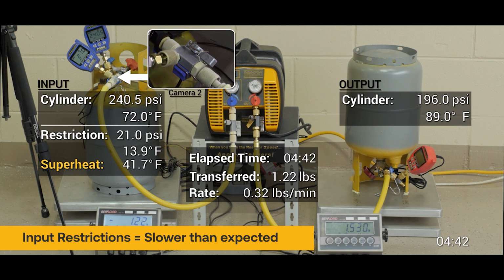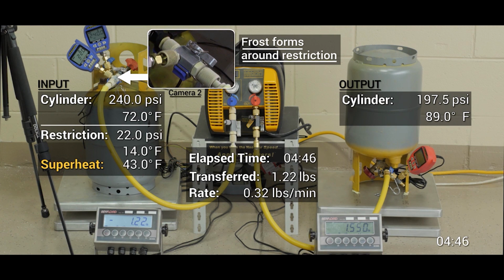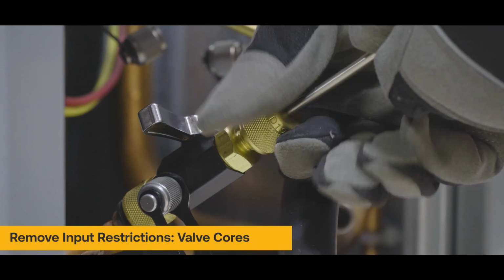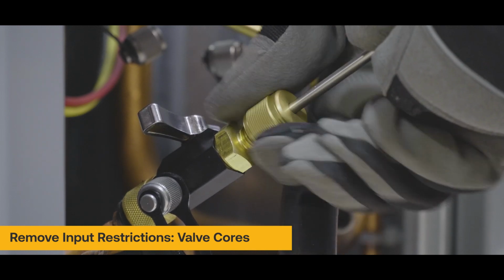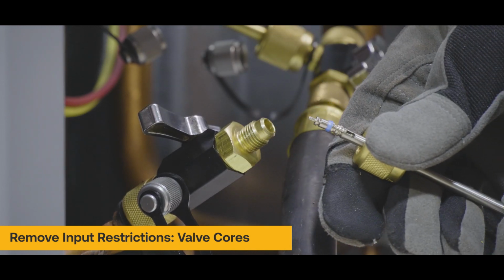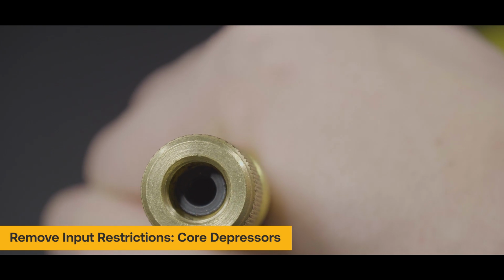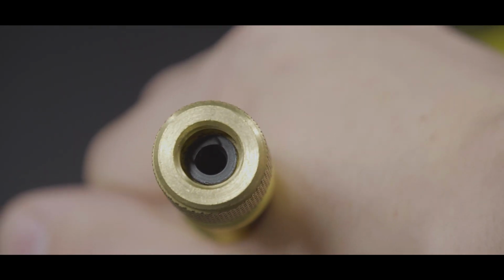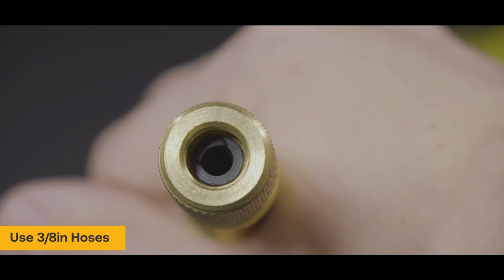Another sign of input restrictions is condensation or frost. This may be at the hose fittings, access valve, or near tight bends in the condenser tubing on the system. Don't get heated up by input restrictions. Remove Schrader valves and core depressors, and use 3/8 hoses to allow full liquid flow to reach the recovery machine.